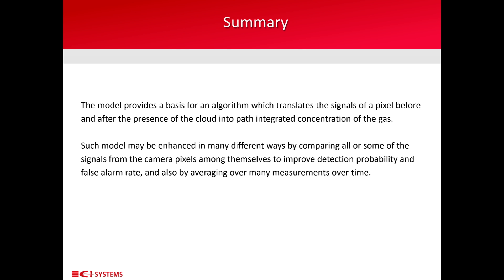In summary, the model described here provides a basis for an algorithm translating the signals of a pixel before and after the presence of the cloud into a path-integrated concentration of the gas once it is detected. Such a model may be enhanced in many different ways by comparing all or some of the signals from the camera pixels among themselves to improve detection probability and false alarm rate, and also by averaging over many measurements over time in order to increase the sensitivity of the system.